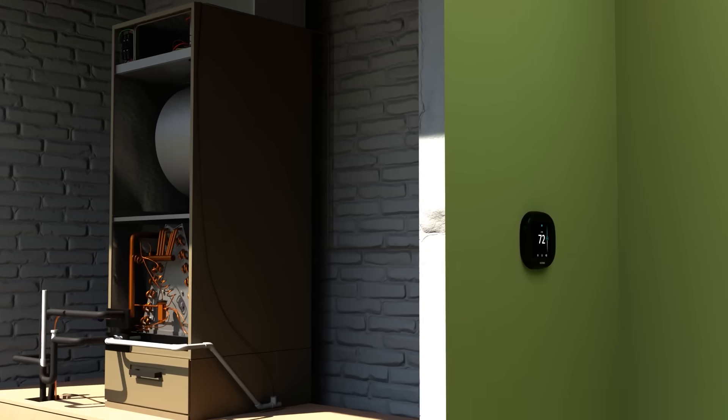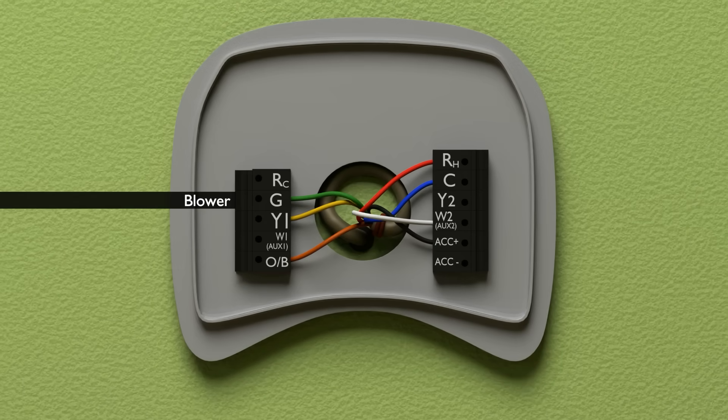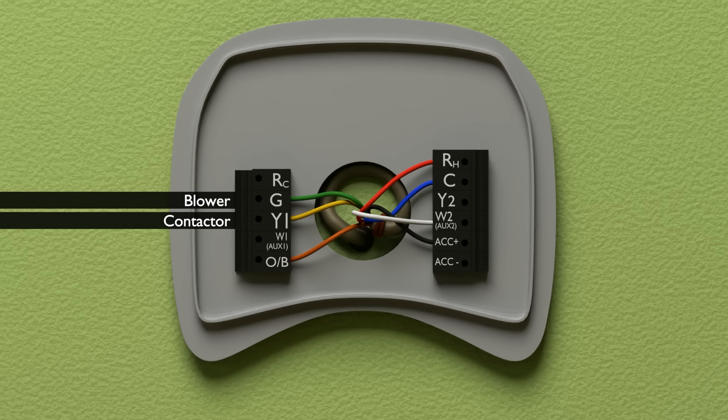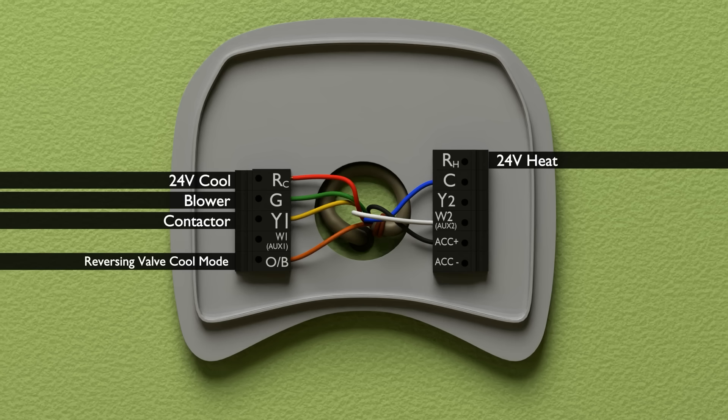Now let's go over our thermostat. G is for the blower call, or 24 volts to the blower motor. Y is the contactor, which turns the condenser on in both heating and cooling mode in a heat pump. O or B is the reversing valve, with O being the most common, orange, which is powering the reversing valve to operate in cooling mode. Meaning that when the system operates in cooling mode, it energizes the O terminal and the orange wire. RH is constant 24-volt power for heating mode, and RC is constant 24-volt power for cooling mode. In most cases, these are the same.